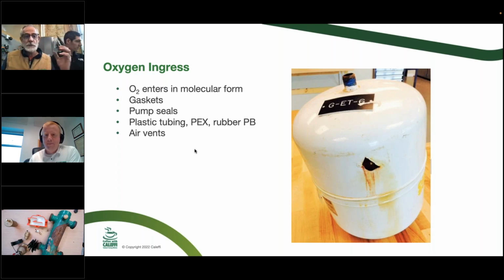So if there's any dirt or rust particles coming through there and it hits that little zone, it has time to settle down. What happens is it'll go on top of the diaphragm or the membrane or the bag, depending on what type of expansion tank you have. It'll sit right on top of that, and then as that diaphragm tries to move up and down, you're kind of abrading the top of it. So come down, put a T in with a branch off, and put your expansion tank off next to it instead of right down below it.